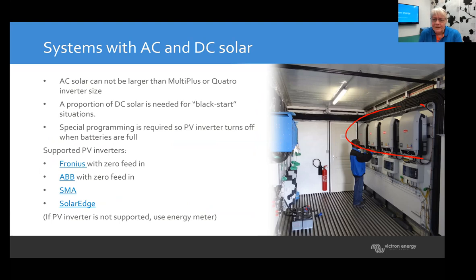But there are a few drawbacks as well. Solar cannot be larger than the Multiplus or Quattro you use. So if you have this many Fronius, or Fronii, I don't know the plural of Fronius, you also need a large amount of inverters, because all the power will go through the inverter charger electronics. So you need to have the same rating as what's coming in. Otherwise, you eventually blow your units up, because it's just built for 3 kVA or 5 or whatever your system is.